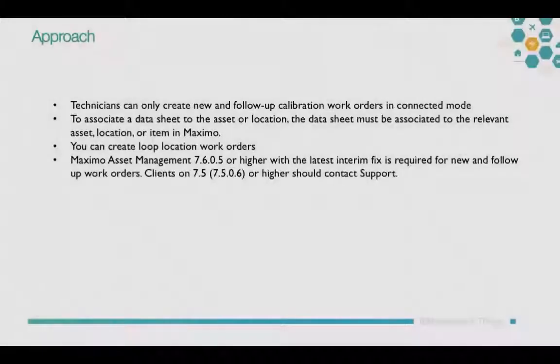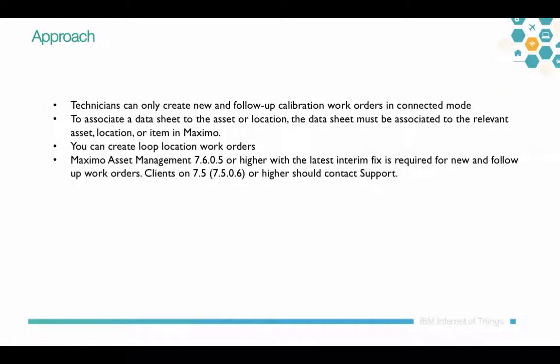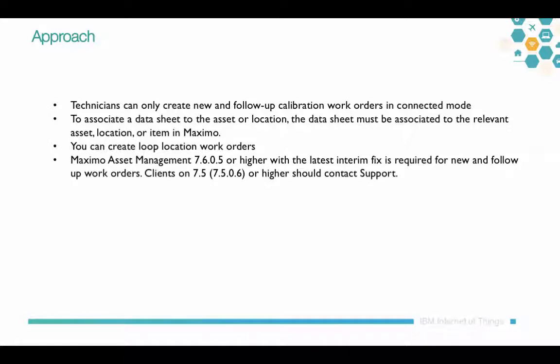A couple of things to remember about the approach we're taking: Calibration technicians can only create new and follow-up calibration work orders in connected mode right now for 7.6.1. To associate a datasheet to the asset or location on the work order, the datasheet must be associated to the relevant asset location or item in Maximo.